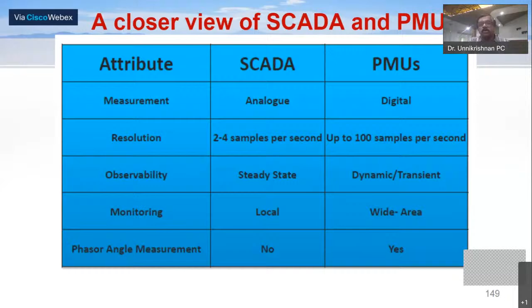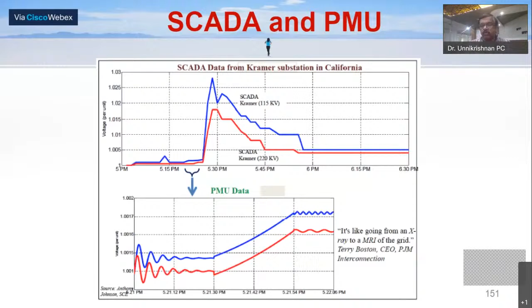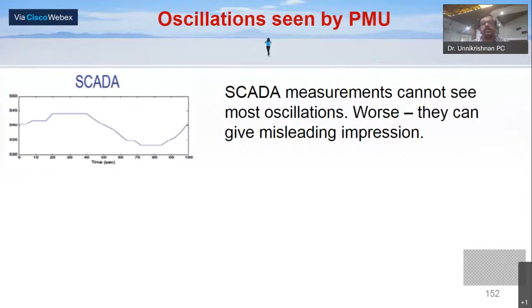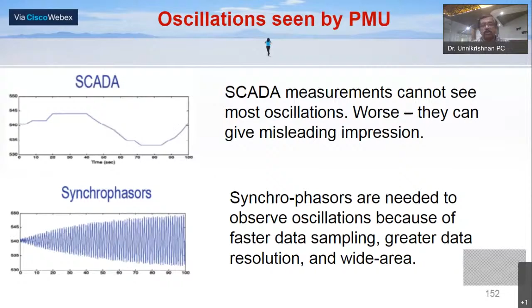If you see this picture, you can see the time between 5.21 and 5.22. In the first picture, it is almost flat, but when you see it from a PMU, you can see the oscillations. The first one is a picture from SCADA, data from a Kramer substation in California, whereas the second picture is from a PMU. So very minute dynamic oscillations can be visualized by PMU outputs. SCADA measurements cannot see most oscillations, so they can give misleading impressions, whereas synchrophasors are needed to observe oscillations because of faster data sampling, greater data resolution, and wide area.